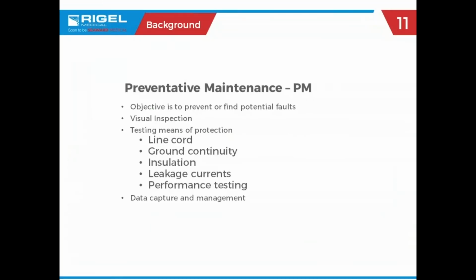So, elements of preventive maintenance, planned preventive maintenance, because typically this is done on some kind of cycle, usually annually. It starts off with a visual inspection. If you thought this was just going to be stand up and have somebody talk to you, no, doesn't work that way. But anyway, we start off with the visual. How many of the issues you find with medical equipment do you find doing visual? The majority, right? Yeah, I mean, line cords, like the photo from Ralph Nader there with the tape around the line cord. That's where most of the issues are. Once you get past there, you have to do performance testing certainly on pieces of equipment, but most of your errors will be found during your visual inspection.